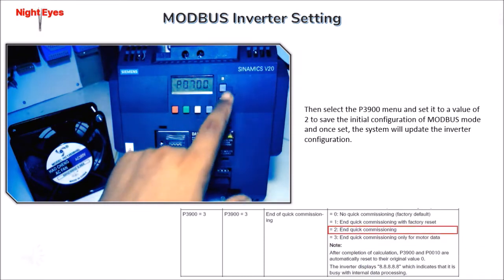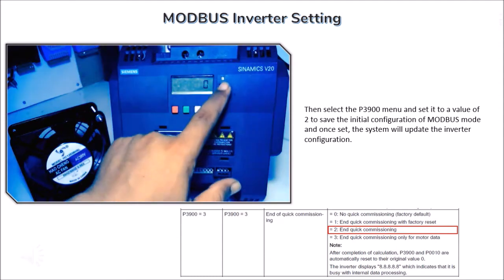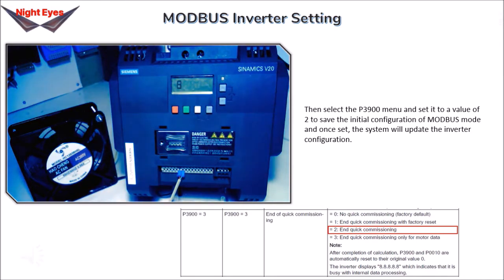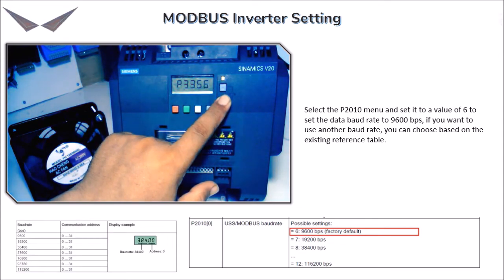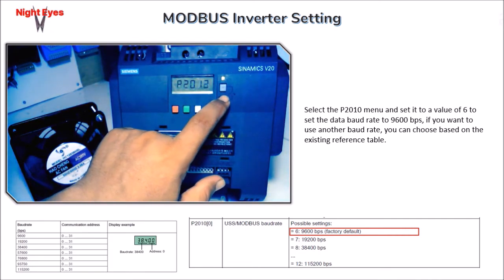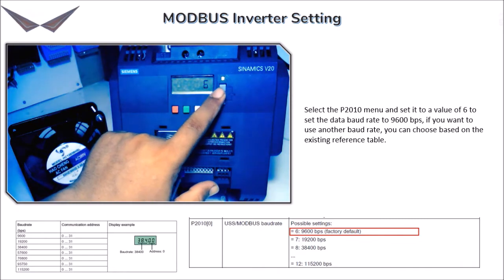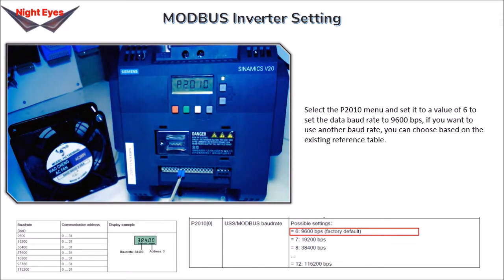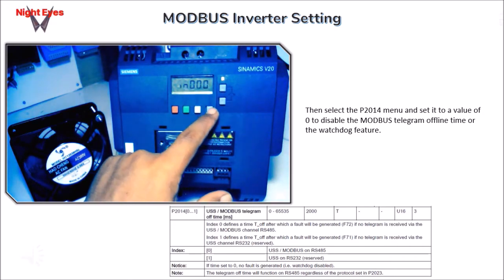Select P3900 and set it to 2 to save the initial Modbus configuration; once set, the system will update the inverter configuration. Select P2010 and set it to 6 to set the baud rate to 9600 bps — other baud rates can be chosen from the reference table. Then select the P2014 telegram timeout menu and set it to 0 to disable the Modbus telegram offline time or watchdog feature.